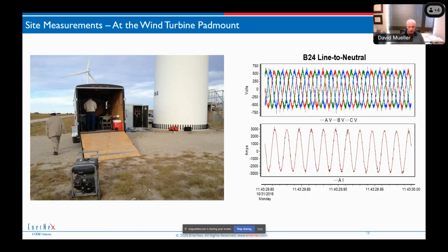This is a measurement from a wind plant where we actually measured. You can see the pad mount transformer. It's de-energized at the moment. We're hooking up our probes. We actually see higher voltage harmonics than we see current harmonics at the 690 volt level. The bottom graph is current and the upper graph is voltage. This is fairly common when you measure inverters at their output. You'll see a higher amount of distortion on the voltage. It kind of falls in line with the voltage source converter, or voltage source of harmonics, if you will.